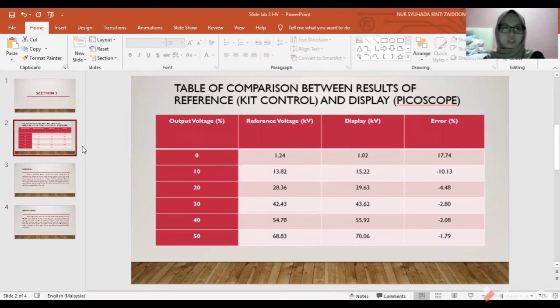Firstly, we are required to construct the table of comparison between the result of reference from the kit control and also the result from the display that was obtained from the picoscope. Basically, this is the table of data that was obtained, and then the percentage of error was calculated. The percentage of error is calculated with reference voltage minus display voltage, divided by reference voltage, and then times by 100%.